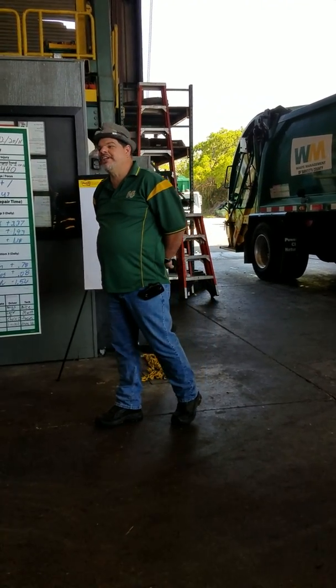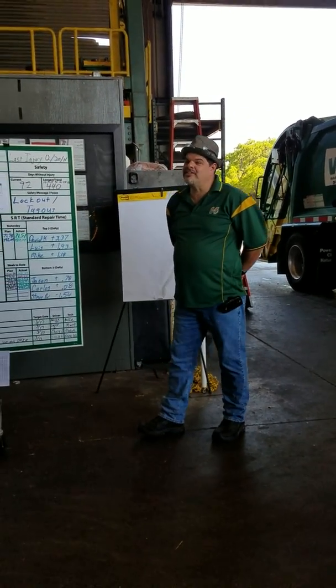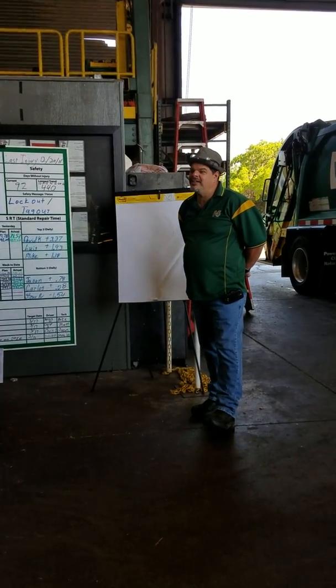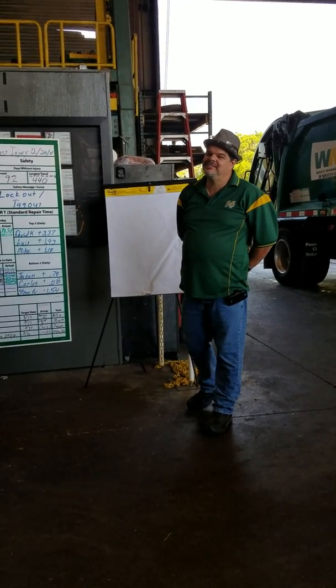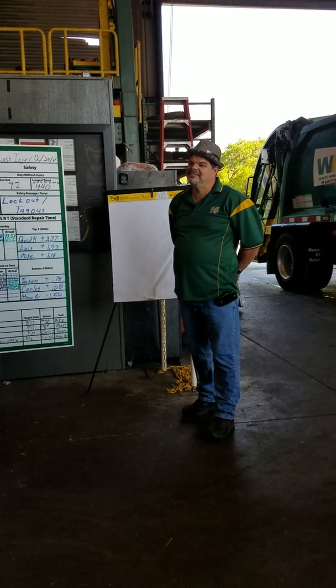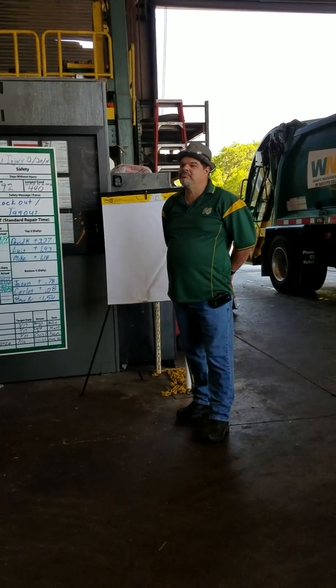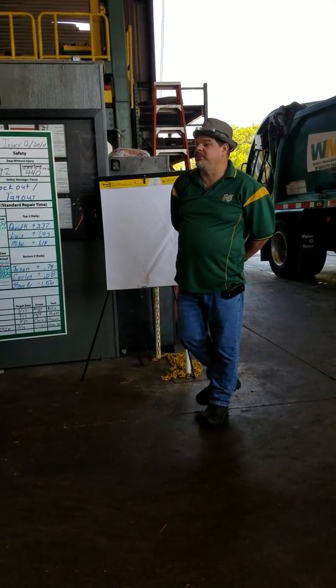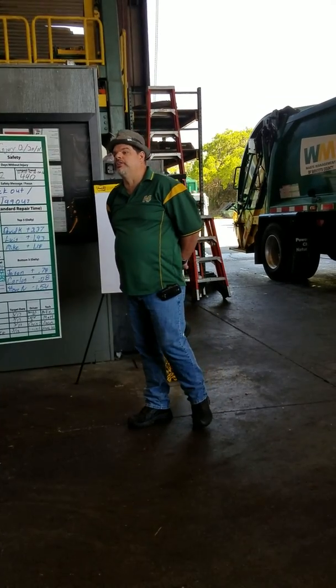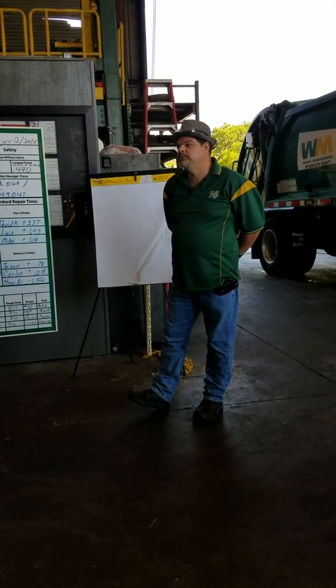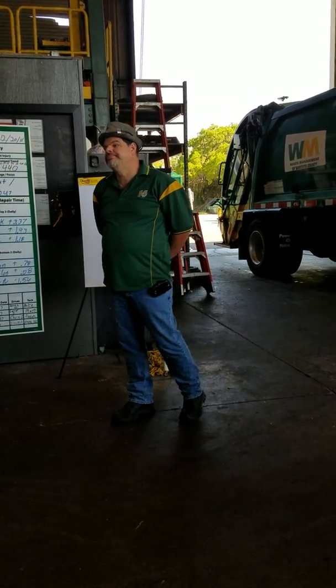So when do we want to check it? Before it starts up in the morning. Yeah, in the morning. We found that works perfect. Cool down at night, then on the launches we've got to watch for it. Look for steam, an excessive amount of moisture coming out of the exhaust, and smell.